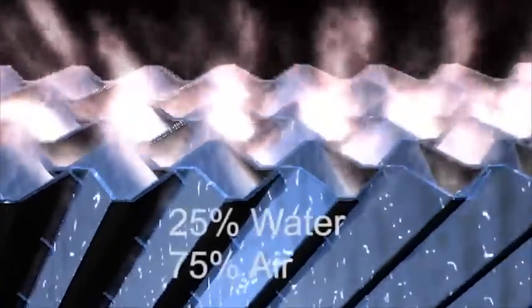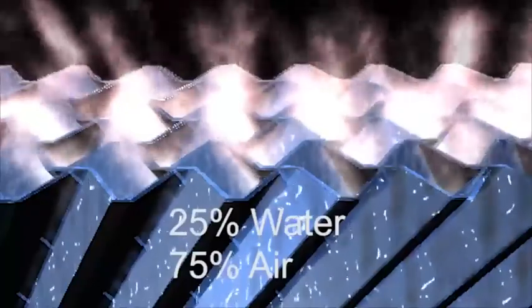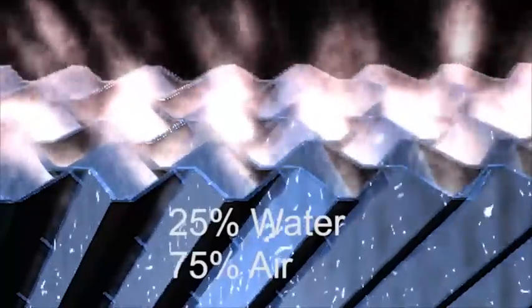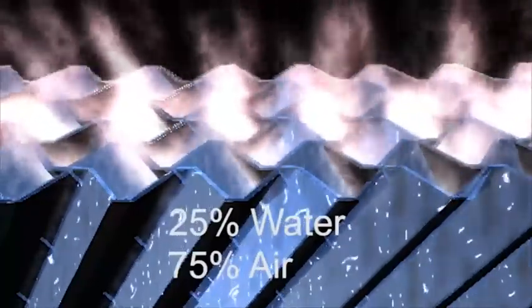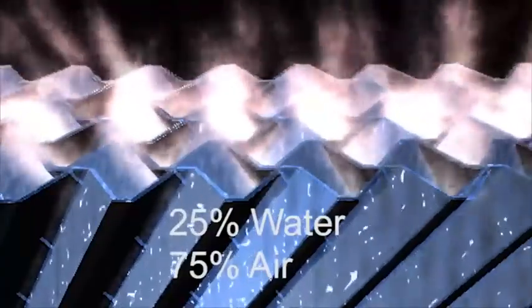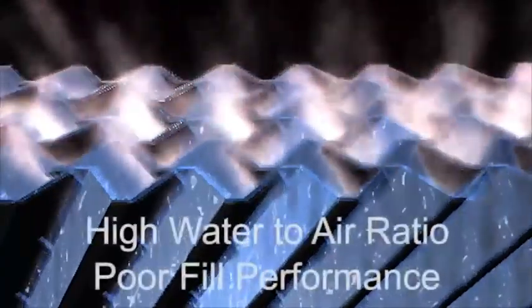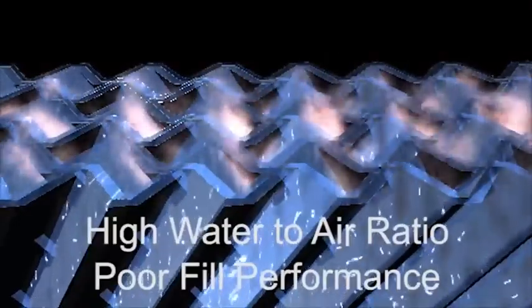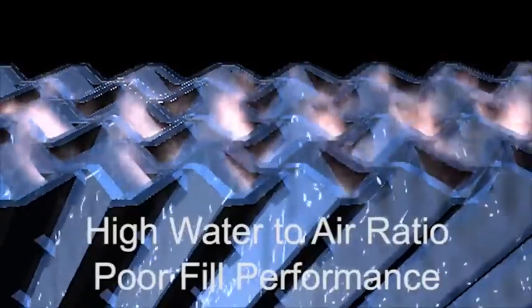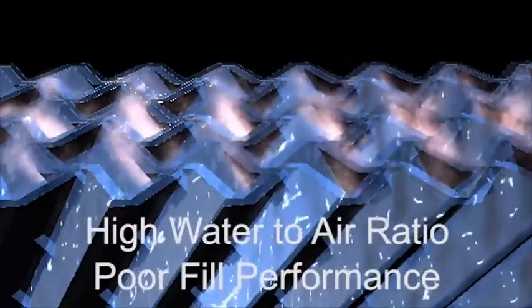First, let me tell you how film media works. Cellular film media consists of a series of corrugated flutes bound together to form a log. Each of these flutes, in essence, becomes a small cooling vessel specifically designed to accommodate 25% of the flute opening being allocated to water loading, and the remaining 75% flute opening dedicated to airflow.